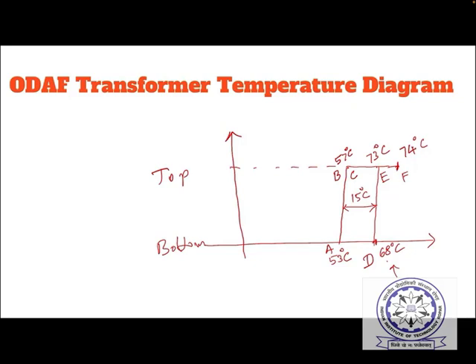So this is how the ODAF transformer temperature diagram will look like, and this is the final arrangement in which greater power can be handled by the transformer. So therefore, outside you have fan cooled, forced air cooling, but outside even water can also be used. That is also, forced water cooling is also possible. But inside, having directed flow of the oil, we can achieve greater power density in the transformer.